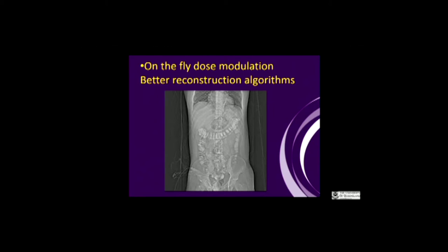This is how we avoid radiation. Nowadays we're decreasing it on CT through several techniques. This is a scanogram — before the CT scans, the machine takes a quick low-dose picture and determines where it needs radiation and where it doesn't. It drops the amperage through parts of the chest where little radiation is needed, increases it through the liver and bowel where more is required, and even increases further down in the pelvis. Instead of giving a blanket dose of radiation, it on-the-fly reduces the radiation so you get the minimum needed to get a good image. It also uses mathematical reconstruction techniques.